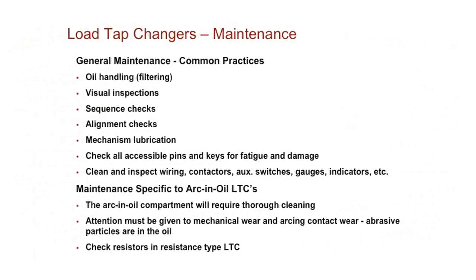Also, during the maintenance, you're doing sequencing checks, alignment checks. This is all part of your timing sequence. Timing is very critical on a tap changer. You want to make sure that your tap changer doesn't get out of step or out of time. Also, you want to check all the accessible pins and keys for fatigue. Mainly this is outside the cabinet on the tap changer that you're looking at.